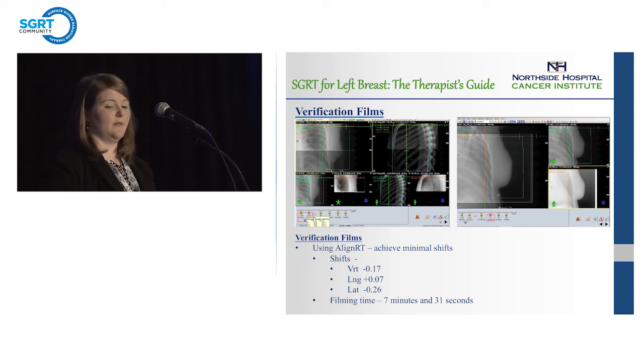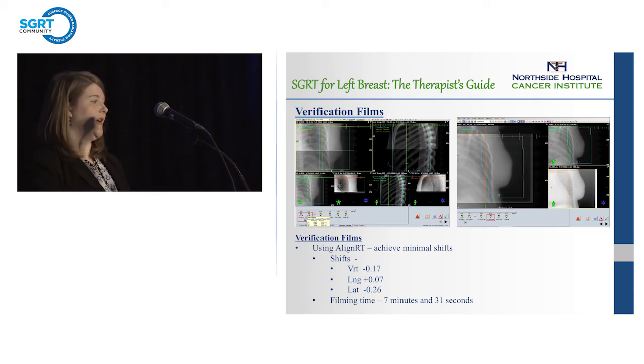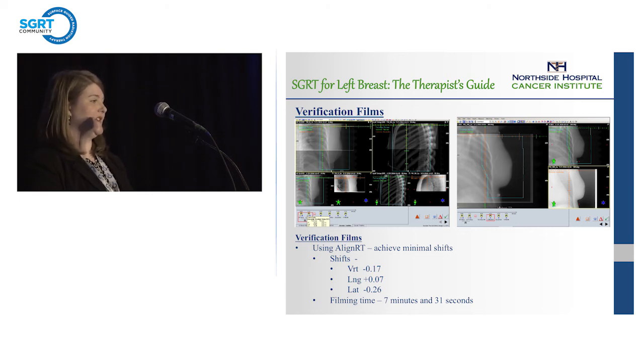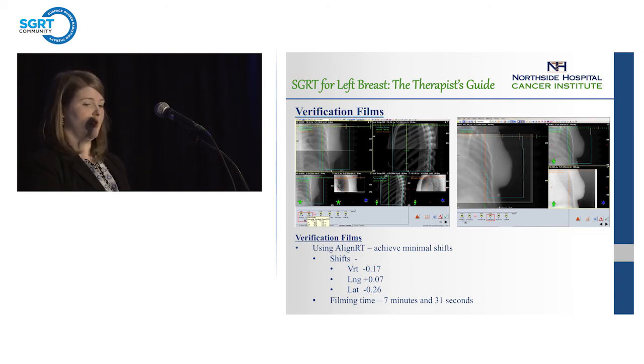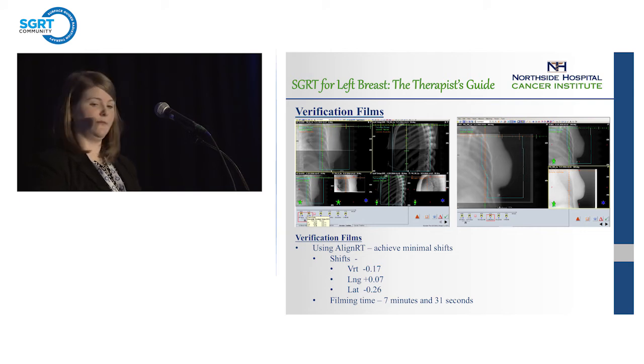That speaks volumes — on any of our other treatment machines, shifts are half a centimeter at least on other patients. The total filming time for this patient's complete verification process was seven minutes and 31 seconds. We were able to do all of her films, acquire all new reference images, and make sure everything was perfect in a minimal amount of time.